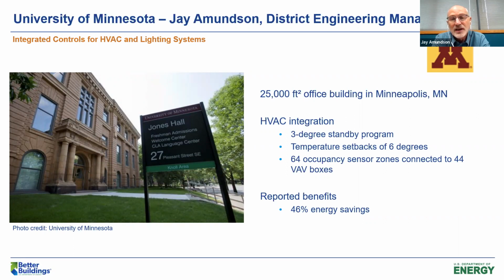So the beauty is that instead of having a classroom's occupancy driven on a time schedule—building open at 6 in the morning, closed at 10 at night—it allowed us to switch those VAV boxes to a standby mode. Occupied is one mode, unoccupied is another, and standby let us drop the temperature a few degrees, but not so much that it couldn't recover in just a few minutes if somebody walked back into the room.